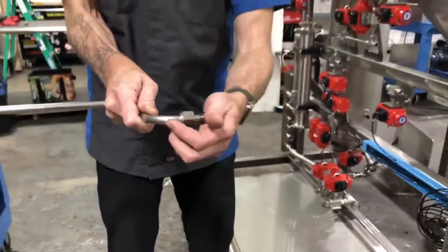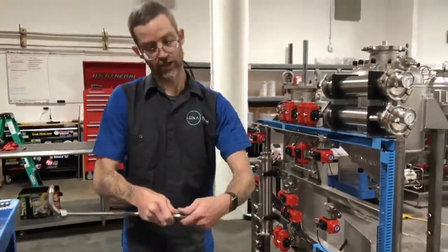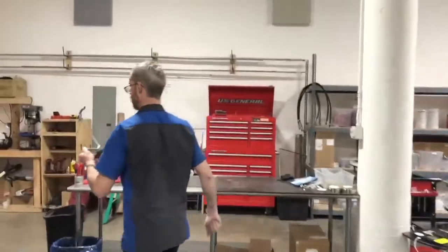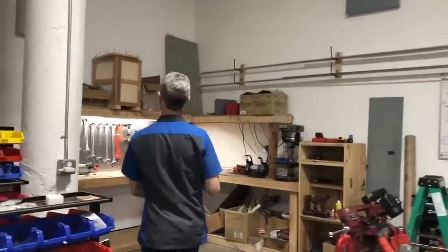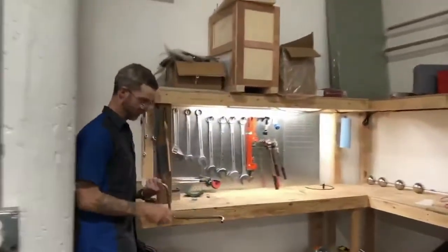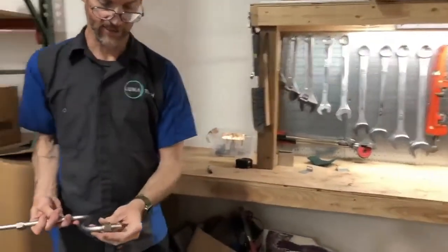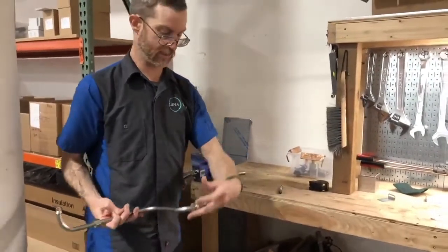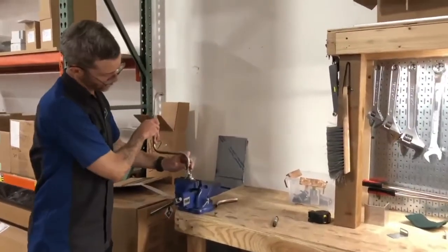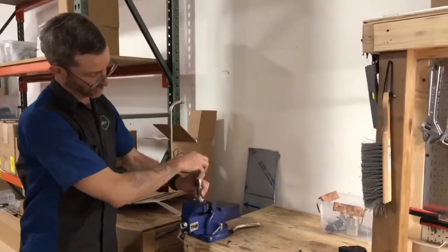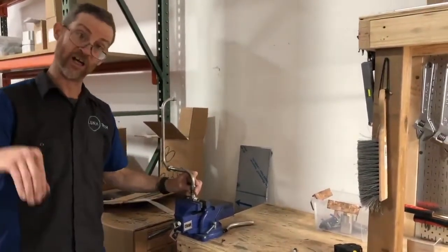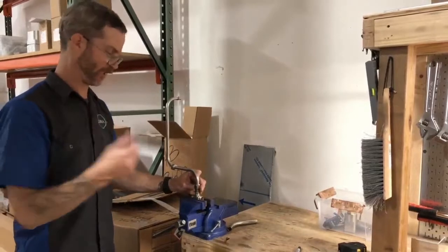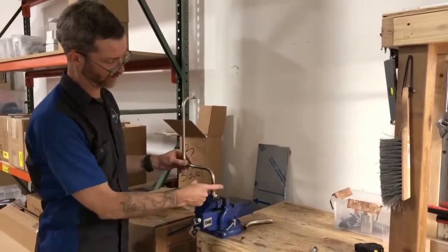Let's come over here first. We need to swage that nut and ferrules onto the end of this tubing. So you saw how I had those oriented, tapered, and in the correct order. We will insert the tubing all the way until it will not go in any further - that's what we refer to as full penetration.